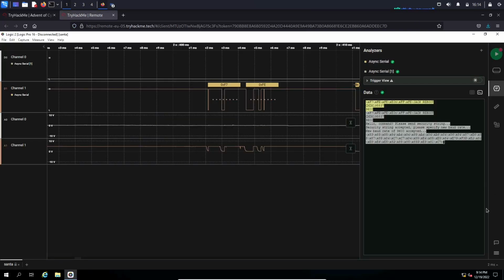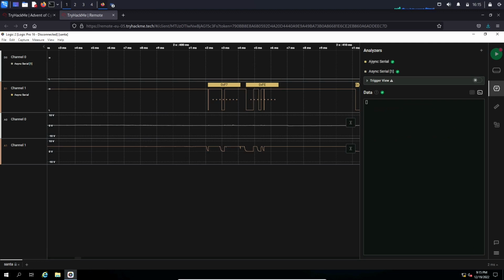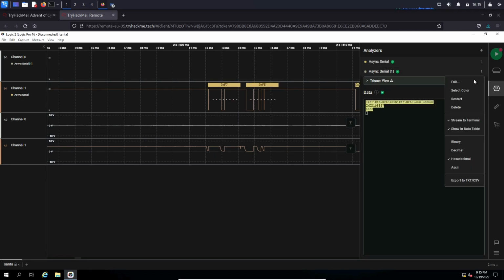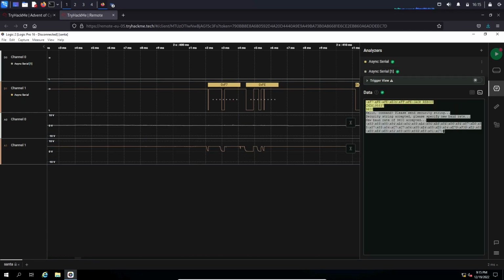So we head into this window and hover down here - the trash icon isn't visible until you hover - and click to clear the terminal. Then we go to the 3 dots next to each one and click restart, and then restart again, and we get a message: ACK reboot, Hello command, please send security string, security string accepted, please specify new baud rate of 9600, accepted.